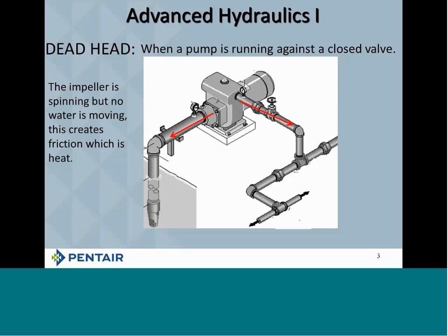So he went ahead and he fixed it, put the pump back in the application, and he still wasn't getting any pressure at the sprinkler heads. He checked the pressure at the pump, and it was working fine. So the next thing he did was he started taking things apart, and right at that first elbow, he found parts of that impeller, and that's what was preventing the water from flowing.